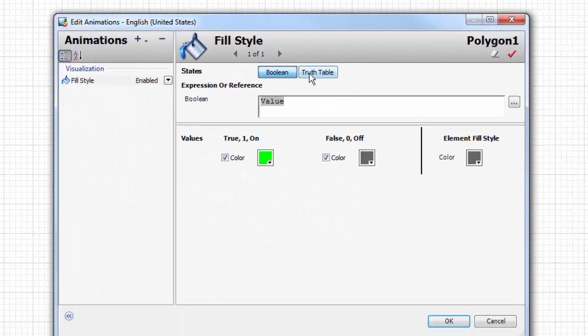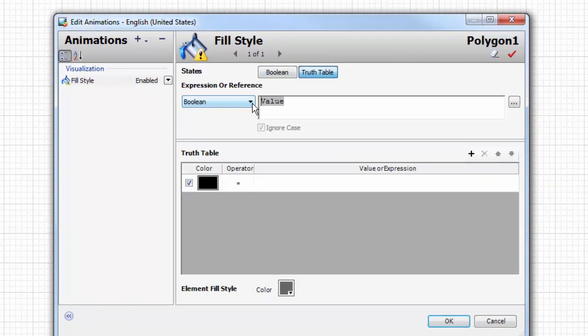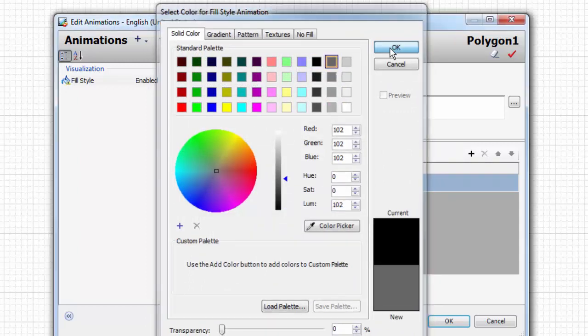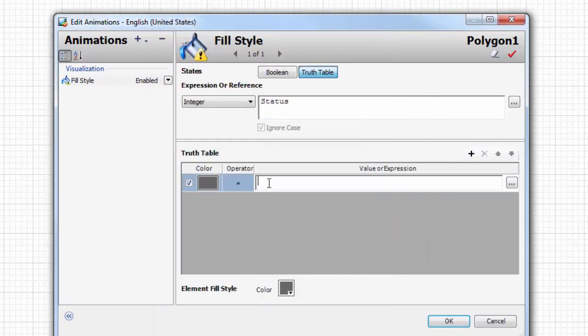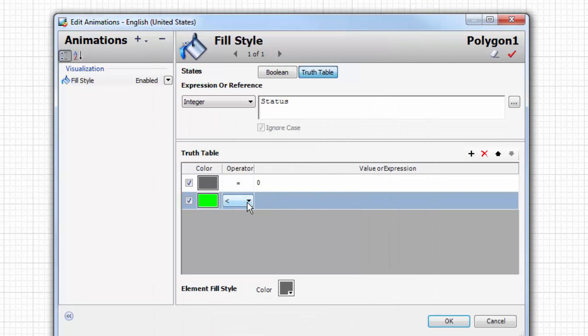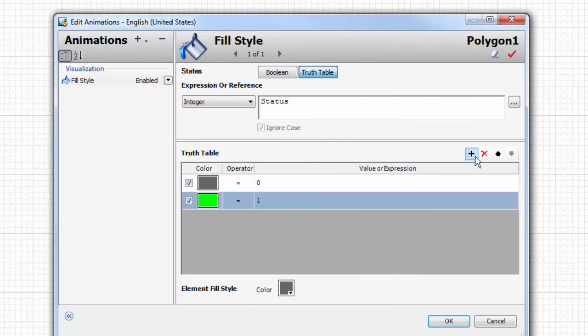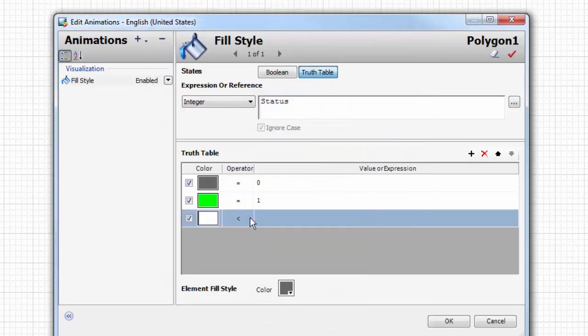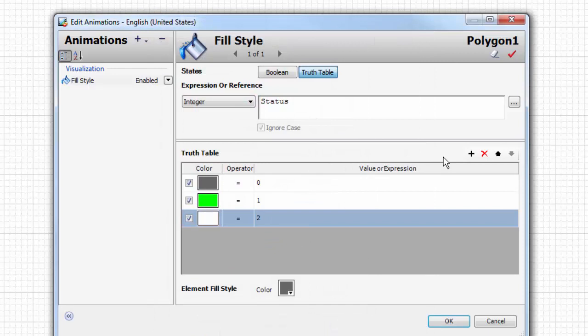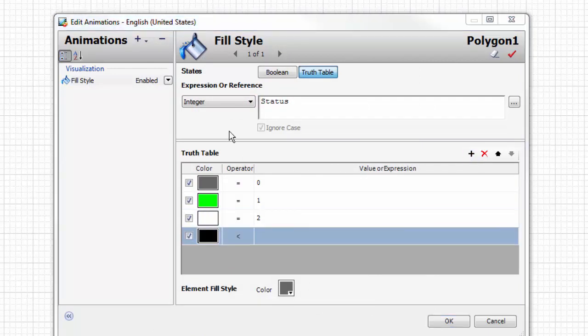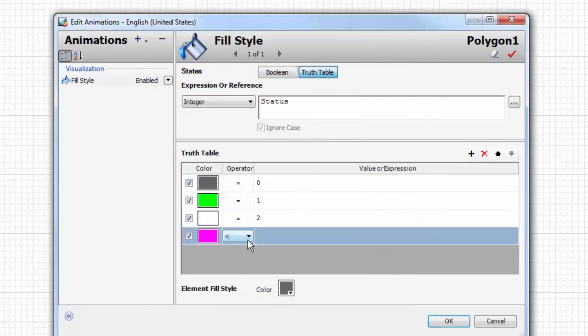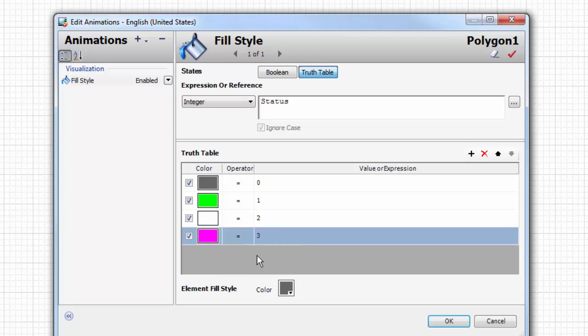In this case we're going to use a truth table instead of a boolean on/off, and it's going to be an integer status. The first color for zero is going to be valve closed, then green will be valve open when it's a one, white will be our travel color when it's a code 2, and then magenta will be our trouble color when it's a code 3. So now we have four states and four colors for this valve. Two switches, four states.